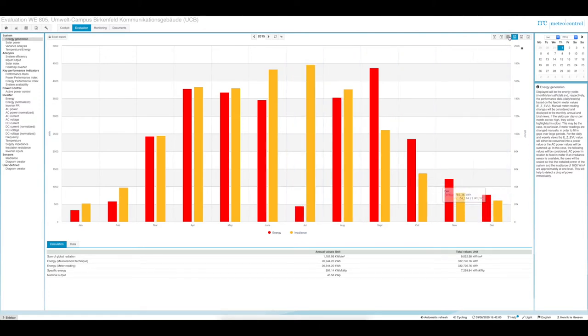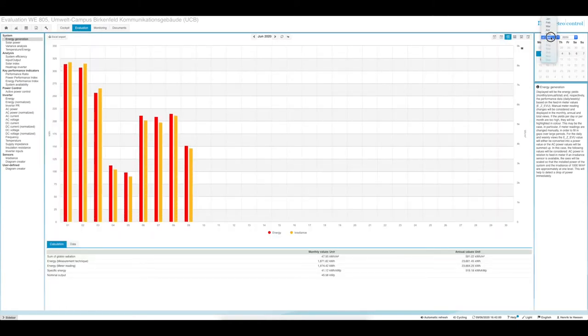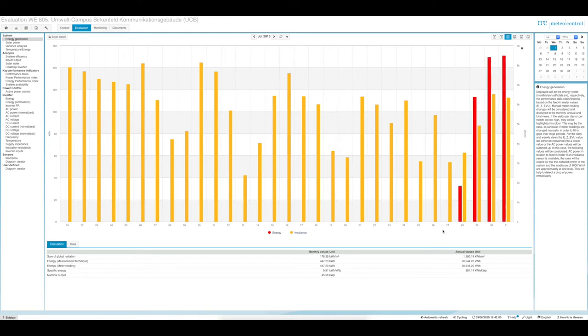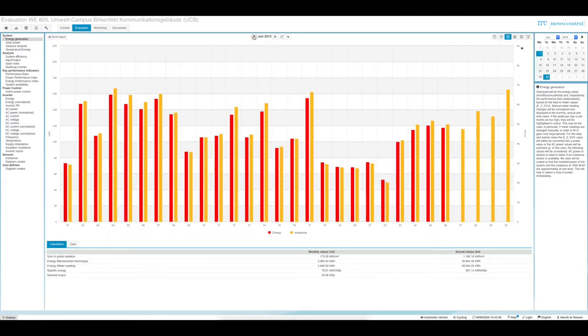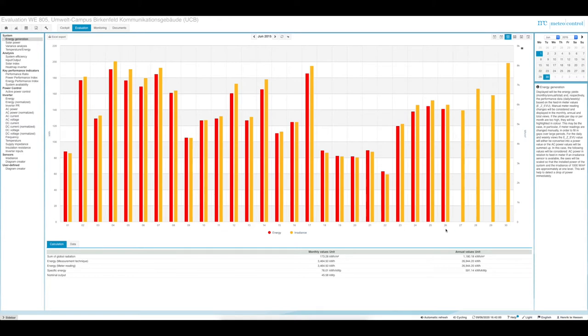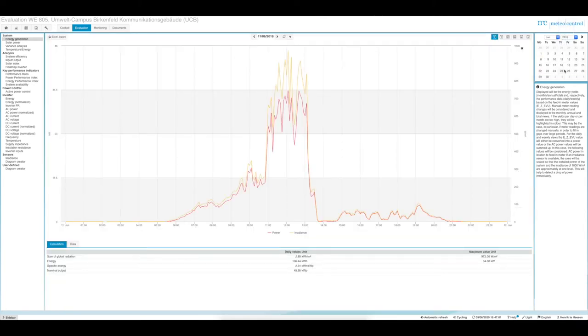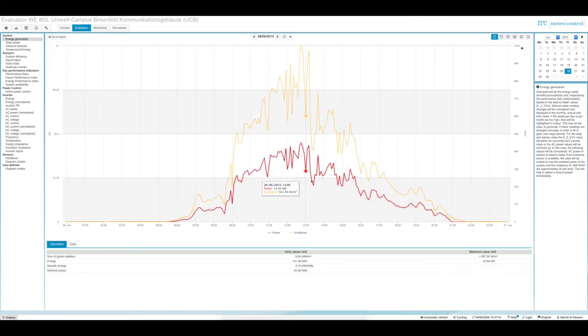Let's have a look at the situation in July 2015 starting from July 1st. We have yellow radiation bars from the 1st to the 27th of July, and then on the 28th we see a red bar. Going back to June, something happened around the 26th of June 2015 — everything looks fine up to that point, and then there's no energy data generated. On June 26th everything is fine with the red and yellow curves, but the next day the power curve is zero — we get data from the radiation sensor but no power generated.